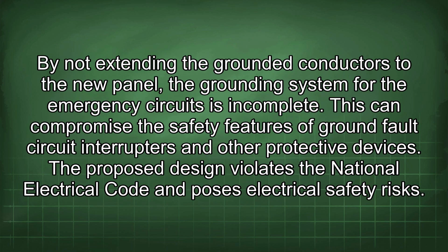By not extending the grounded conductors to the new panel, the grounding system for the emergency circuits is incomplete. This can compromise the safety features of ground fault circuit interrupters and other protective devices. The proposed design violates the National Electrical Code and poses electrical safety risks.